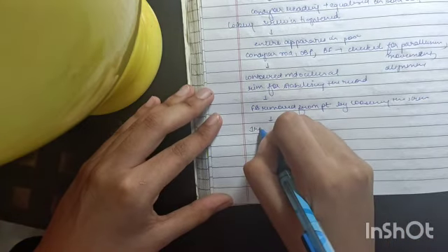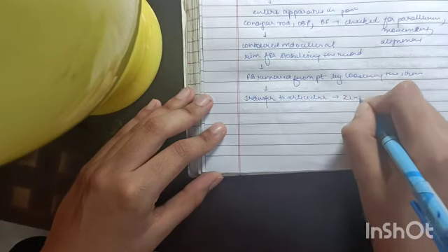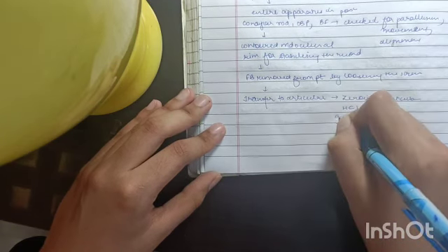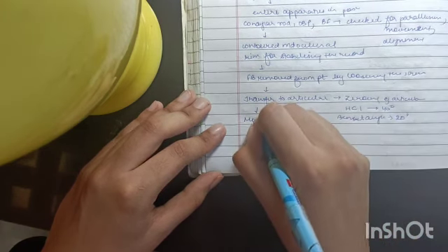Now we will transfer to the articulator. First we will zero the articulator. Now in this, horizontal condylar inclination is set to 40 degrees. Bennett angle is set to 20 degrees.